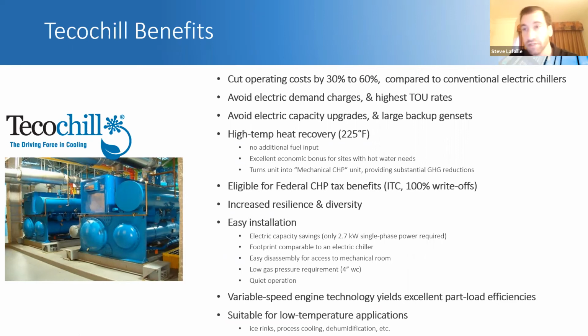Low gas pressure, 4 inches of water column. Pretty much anywhere you have gas needed from the pipeline, you can at least be able to get 4 inches. I mean, it's a quarter of a PSI. So no gas boosters or anything like that. Footprint, very similar to electric chiller. As you can see, the vessels pretty much define the footprint. It can be broken down, just like most electric versions of this, into pieces if needed to rig in.